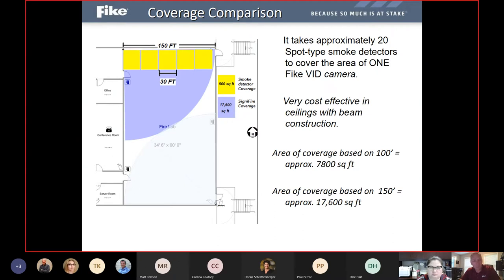Where it becomes very popular is in areas of beam pockets or beam construction in the ceilings. Whenever you need to put a sampling point or a smoke detector up in a beam pocket, it gets rather costly from a standpoint of additional material needed, conduit and wire and installation, as well as the ongoing cost of ownership. With a camera system, we can alleviate that by putting one camera on the wall that's looking directly under all of those beam pockets, and you've now covered every beam pocket with one camera, because anything that's going to enter that beam pocket will be detected by the camera.